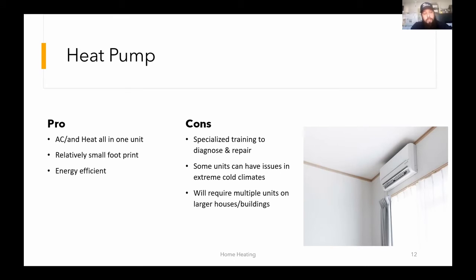We don't do much of those up north because no matter how big we size the heat pump unit, when it's extreme cold we always need a backup as well, because the ground or air-to-air units have only so much heat or cooling capacity to gain from the ground or air. About midway through the winter, or sooner, the heat is sucked out of the ground, and you need another unit to make up for that heat, as there's no more to gain from the ground. So these units have issues in extreme cold climates.